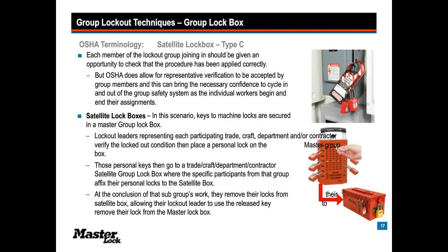Now when the trade finishes their work for the day, they come back, they remove their personal locks. When the last lock is removed, the lockout leader for that team, that special work group, removes their key from the master box, or the satellite box, I should say.